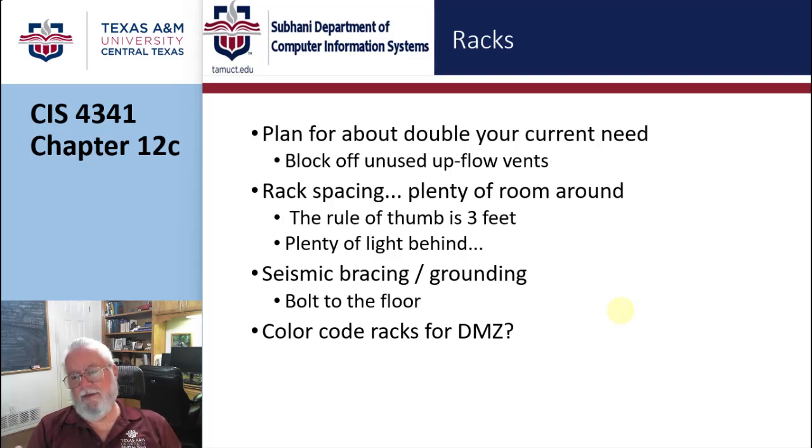One of the stories I love to talk about is, send the guy back and say, okay, we're getting ready to replace the email server. So let's go back there and pull the plug. We already have the guy shut down. Just go ahead and pull the electrical plugs from the dual power supplies. And the guy goes back there with a flashlight and he unplugs the database server instead because he couldn't see what he was doing. And they weren't labeled in the back. The front had labeling, but the back of the rack didn't have any labeling. He couldn't see what he was doing, and he unplugged the wrong thing.